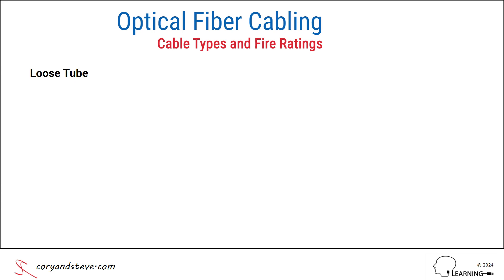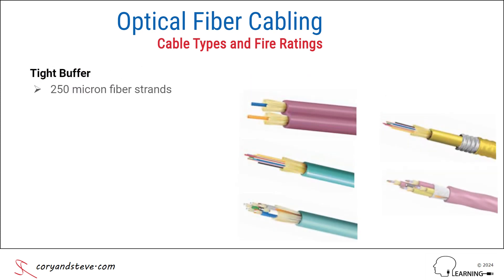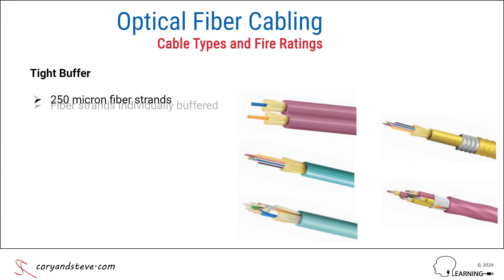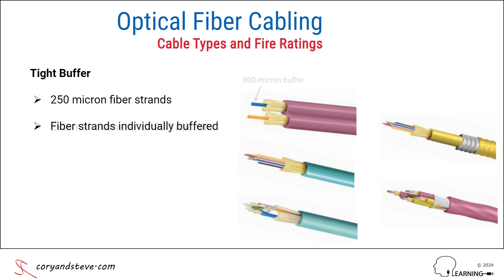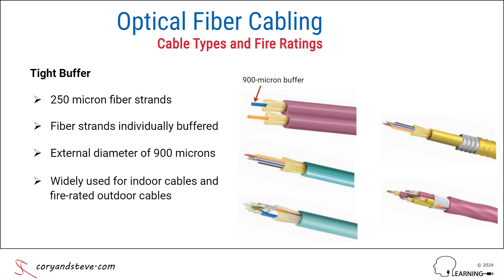The second type of cable construction is tight buffer, where the 250 micron fiber strands are individually buffered or tightly covered with a protective layer, making their external diameter 900 microns, or just under one millimeter, which is equal to 1000 microns. This construction is widely used for indoor cables, as well as for fire-rated outdoor or campus cables, which can be extended and routed within buildings after entry, without the need to transition to a fire-rated cable in the entrance room or entrance space.